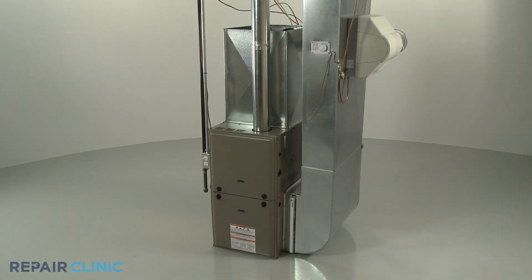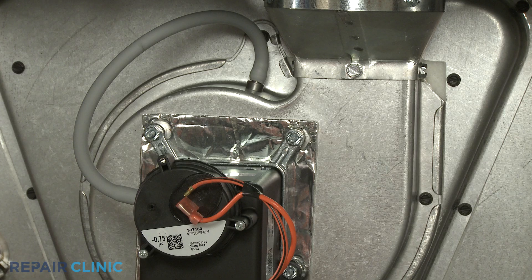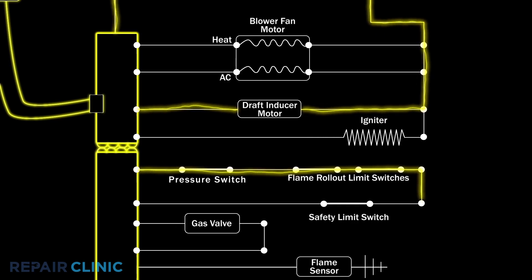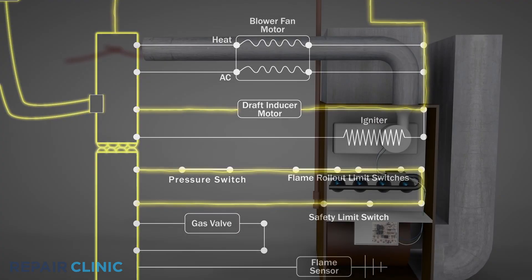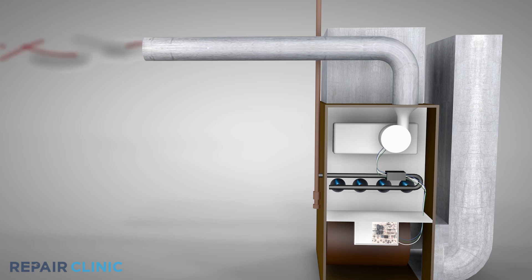If a furnace is not heating, or it continually starts then stops, the pressure switch could be malfunctioning. As part of the furnace's ignition system, the pressure switch will close once the draft inducer fan motor reaches its maximum speed. This is a safety precaution to ensure that gas will not enter the furnace unless the toxic fumes within the burner assembly can be exhausted.